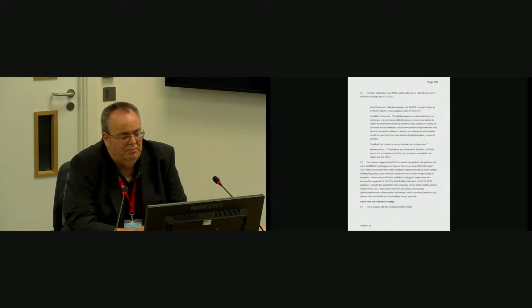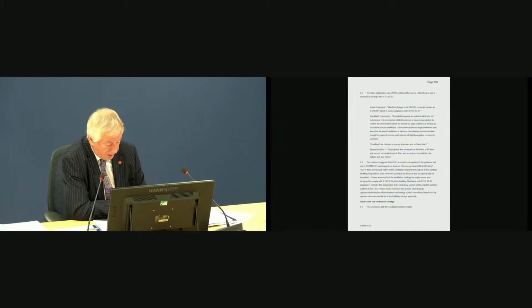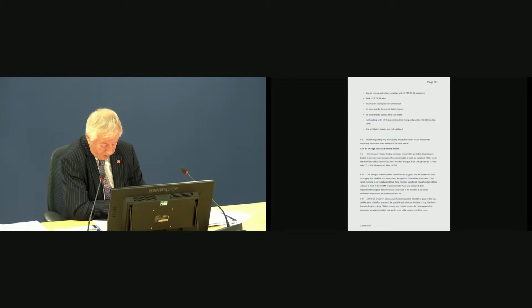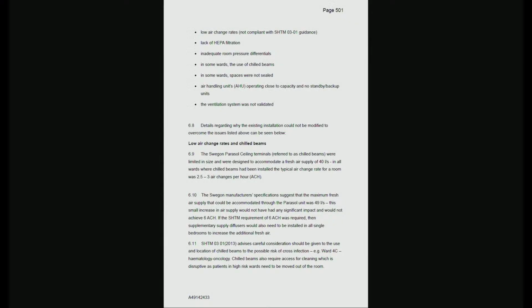Thank you. And what you then do is you list on page 501 a number of the issues that arise from this that you've discovered as you've looked at the material. Low air change rates, lack of HEPA filtration, inadequate pressure differentials, chilled beams, spaces not sealed, air handling that's close to capacity, no standby, and the ventilation system not being validated.